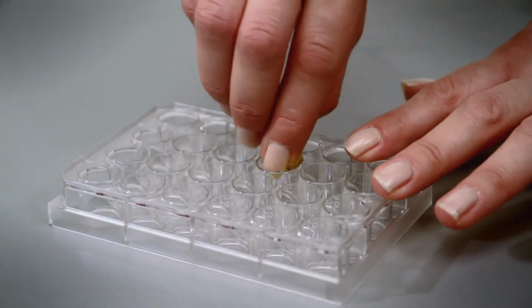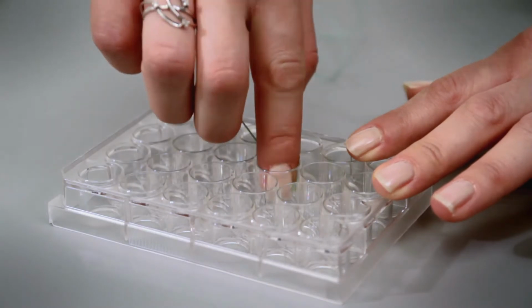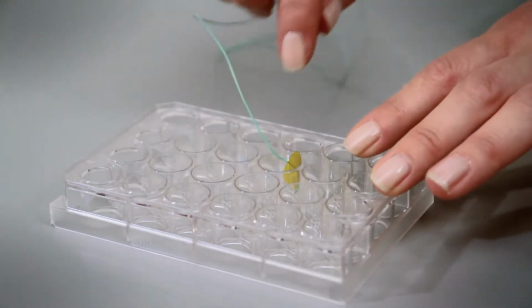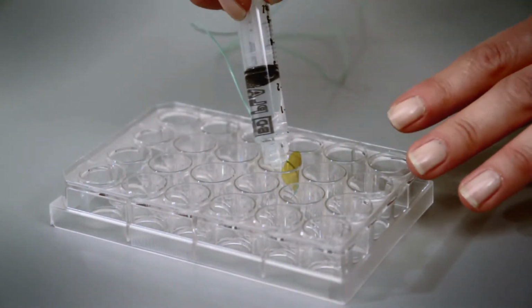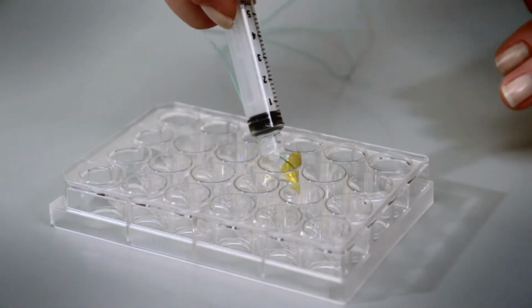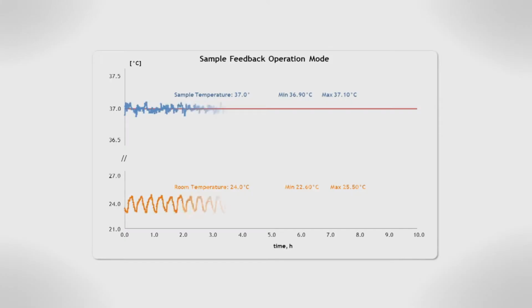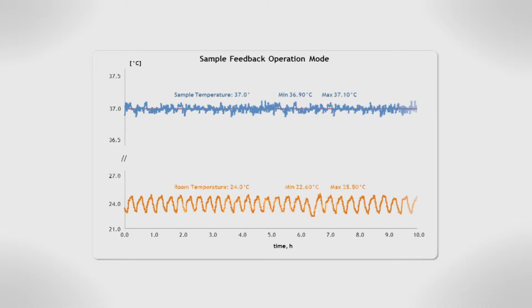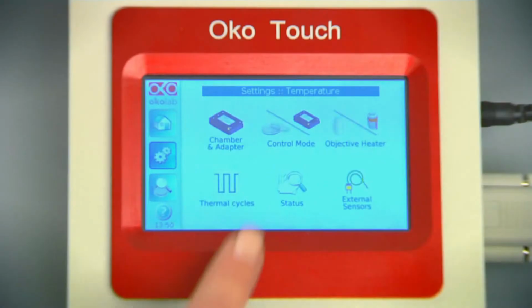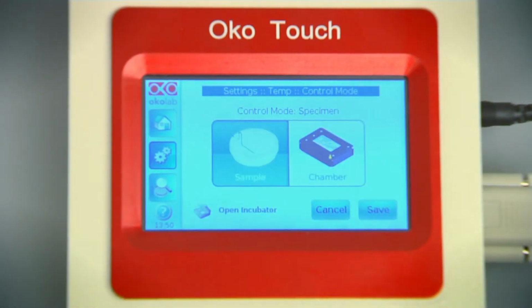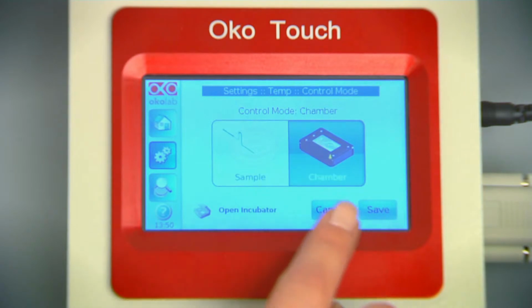If you are employing a multi-well plate, position the green specimen feedback sensor in one of the wells and cover it with water. With this operation mode, sample temperature will remain within plus or minus 0.1 degrees Celsius, regardless of room temperature. If you prefer not to employ a sample feedback sensor, select the chamber feedback operation mode from the touchpad.